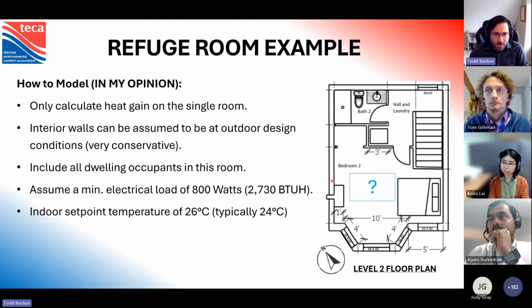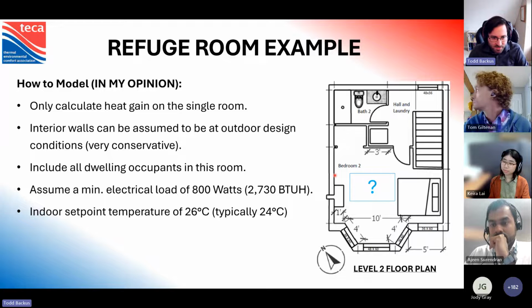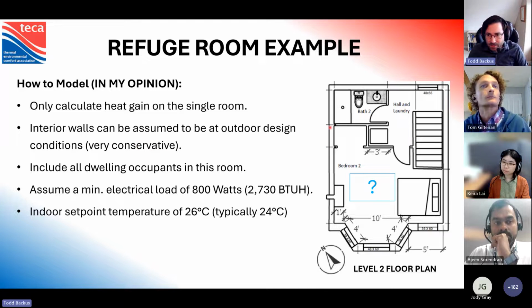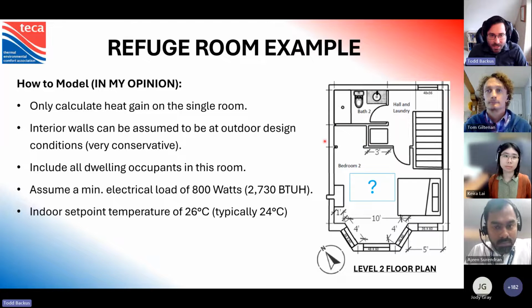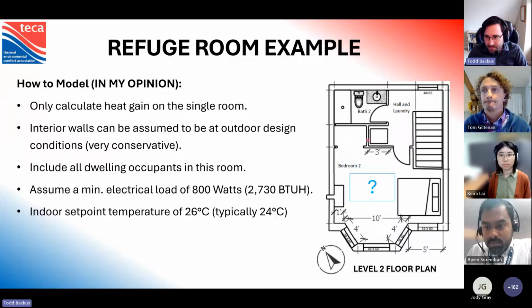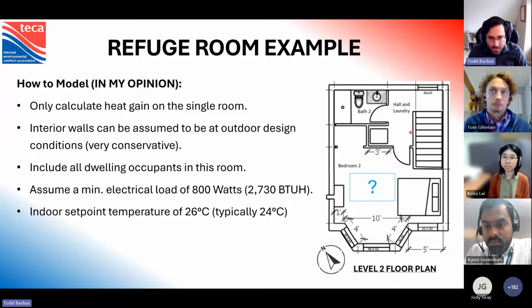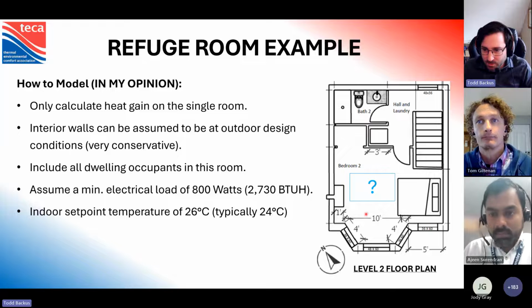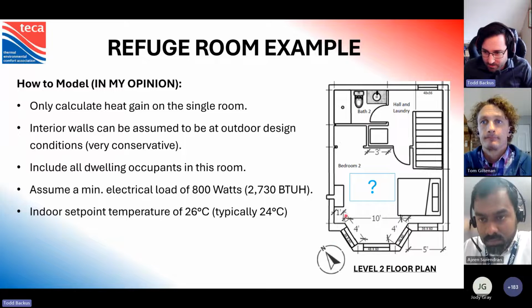So to find the correct number, again, this is how I would do it. This is not laid out in any kind of standard or in the code specifically, but I would treat this one room as its own dwelling. So I would treat all of these interior walls as exterior walls, so the same R value as what's wrapped around here, and consider this temperature to be the outdoor air temperature. It is a very conservative estimate, but the energy transfer through the walls is actually not that big a deal, because as we recall, the biggest loads do tend to come from the windows. So we're not adding any windows over here. This doesn't have as dramatic an effect as it might initially seem.